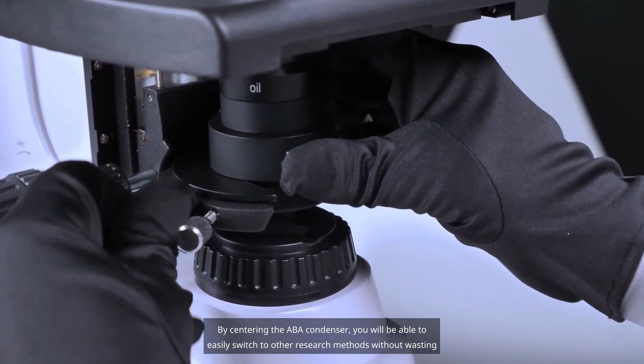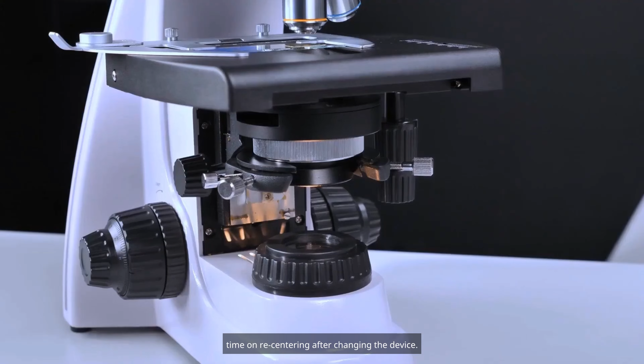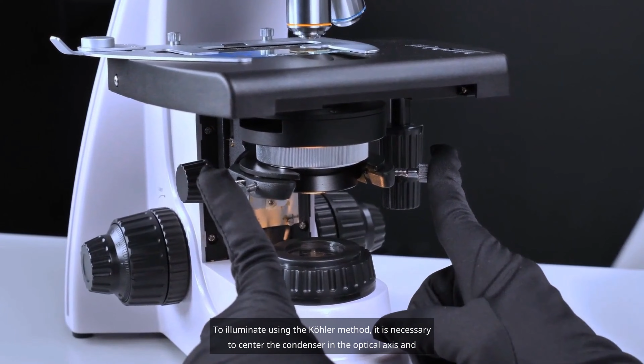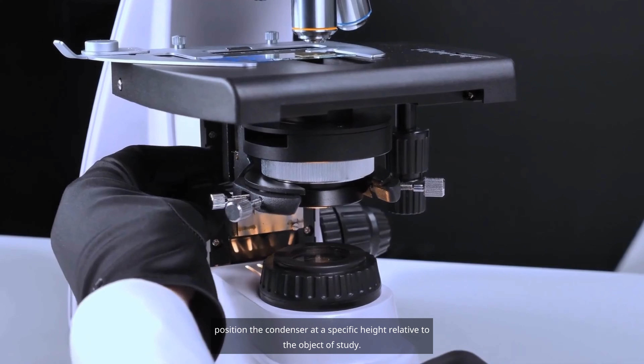By centering the Abbe condenser, you will be able to easily switch to other research methods without wasting time on recentering after changing the device. To illuminate using the Köhler method, it is necessary to center the condenser in the optical axis and position the condenser at a specific height relative to the object of study. The condenser is moved along the optical axis by rotating this knob.